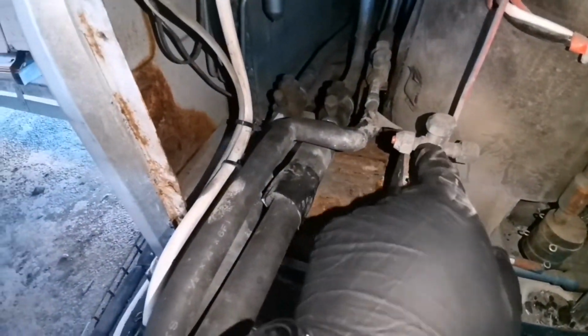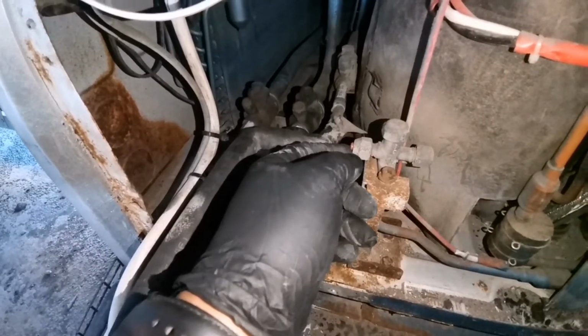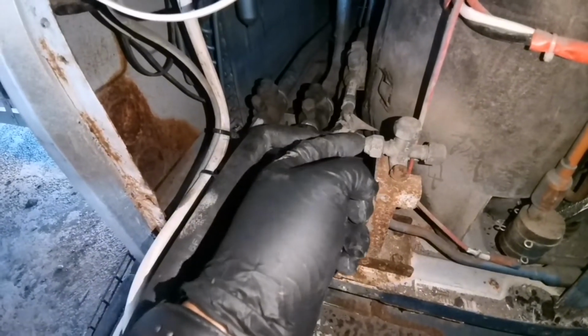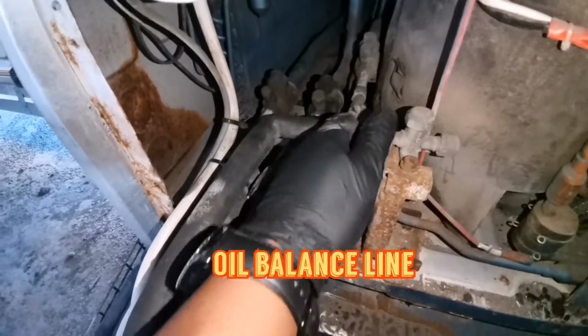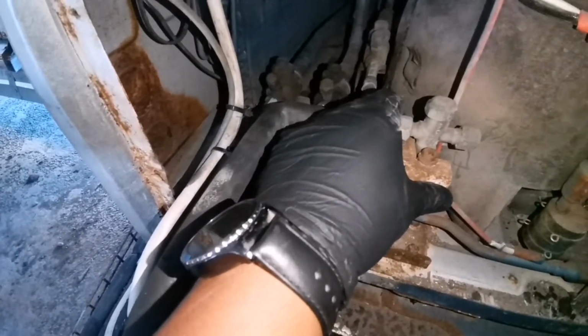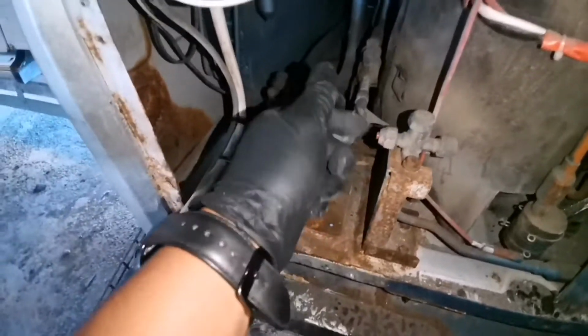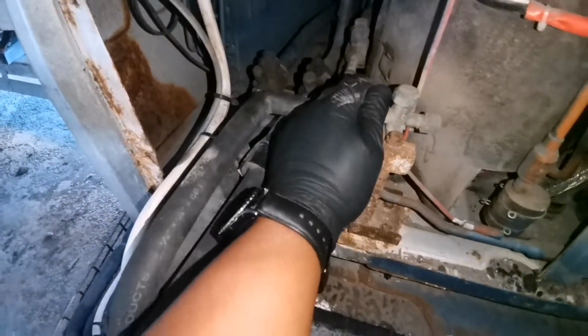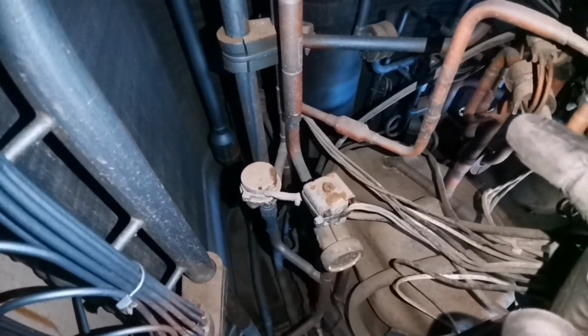Alright, so let me give you guys a sneak peek inside here. At the back there, we've got a plated heat exchanger. So yeah, like I said, we're going to have to take an oil sample. This is our oil port. If you had another condenser linked up to this condenser, you would run another line to that condenser. This is the oil port right here. We'll see, man. Maybe we'll grab a sample from here and just have a visual of how this oil looks. But we're going to have to check the accumulator return valve to ensure that it is functioning properly.